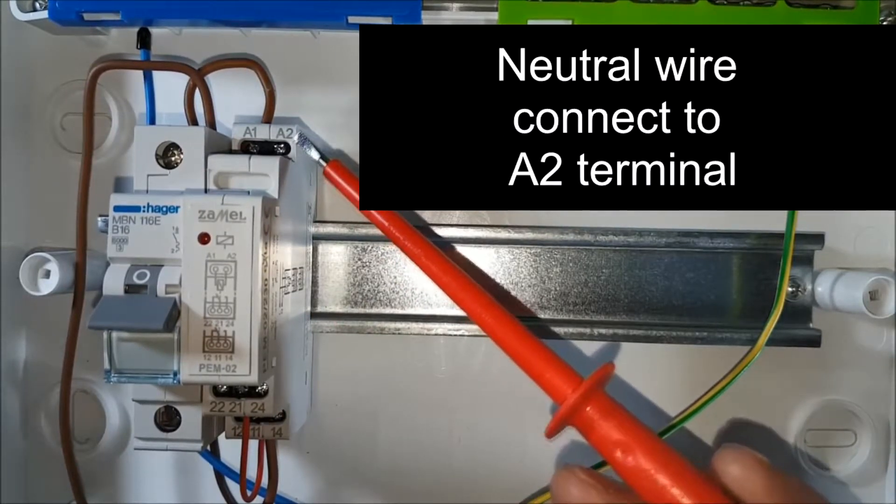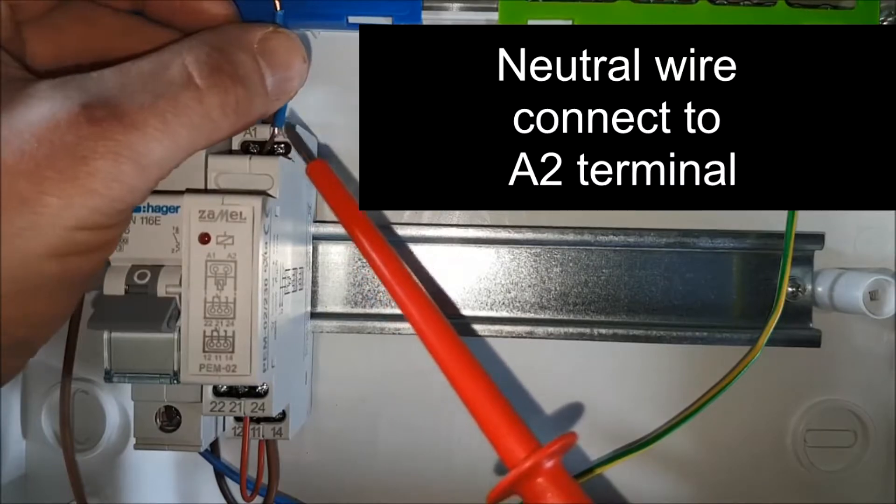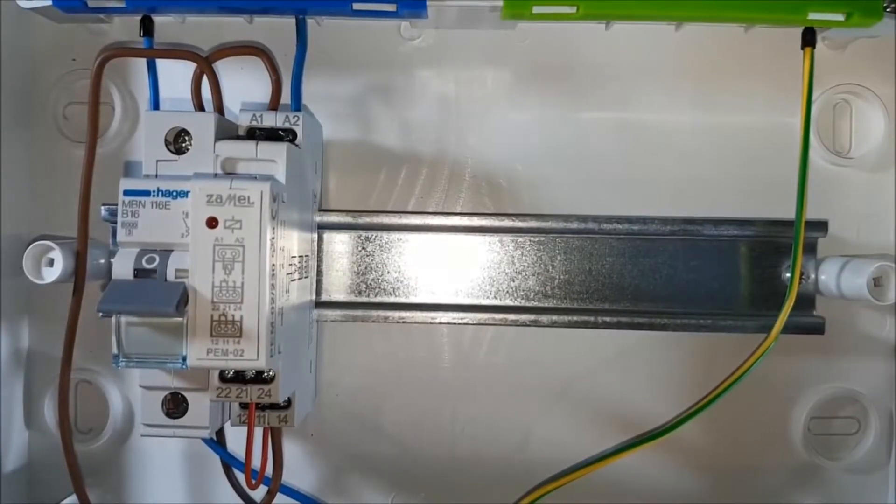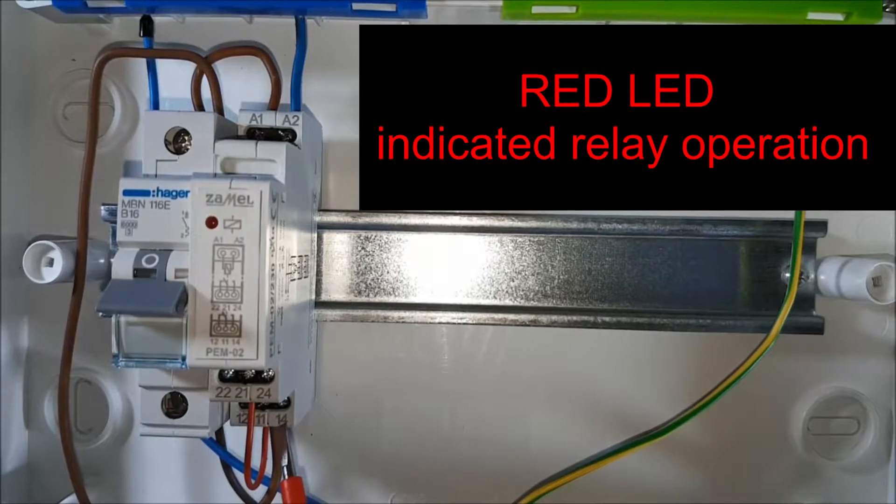Neutral wire, connect to terminal A2. Providing power supply causes the relay to start. This is indicated by a red LED. Output voltage appears on the output terminals 14 and 24 of the relay.